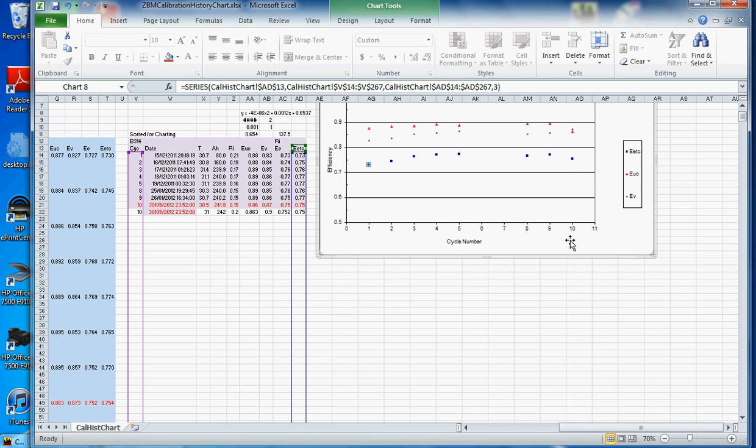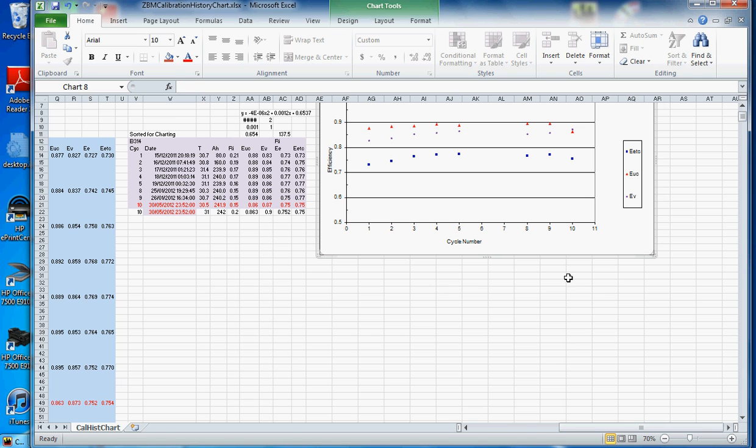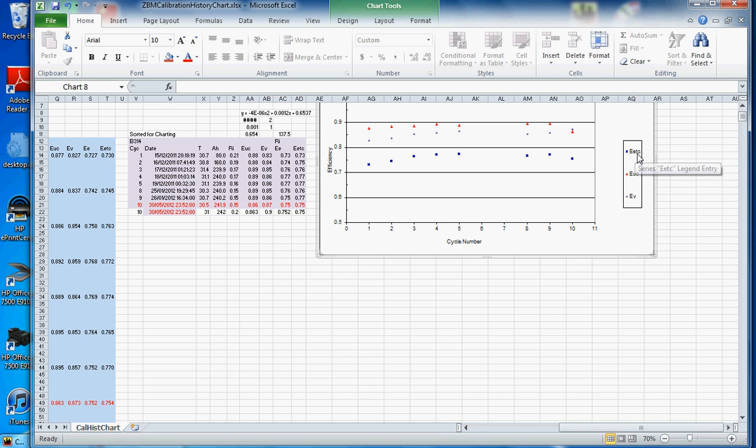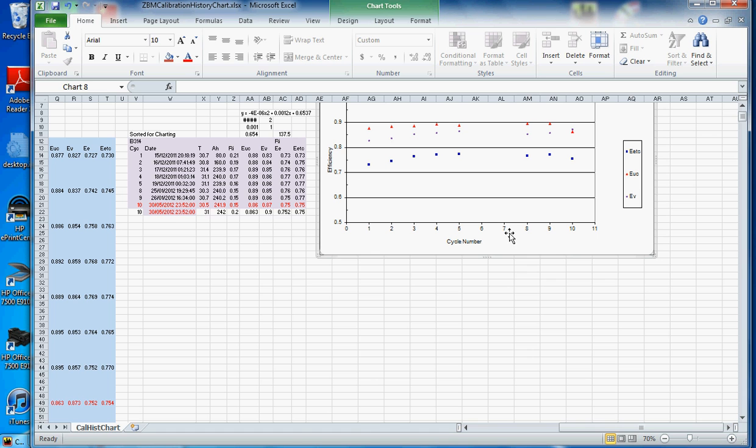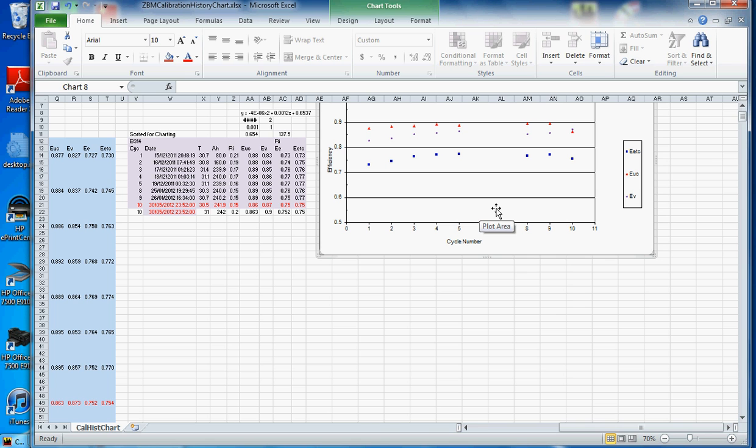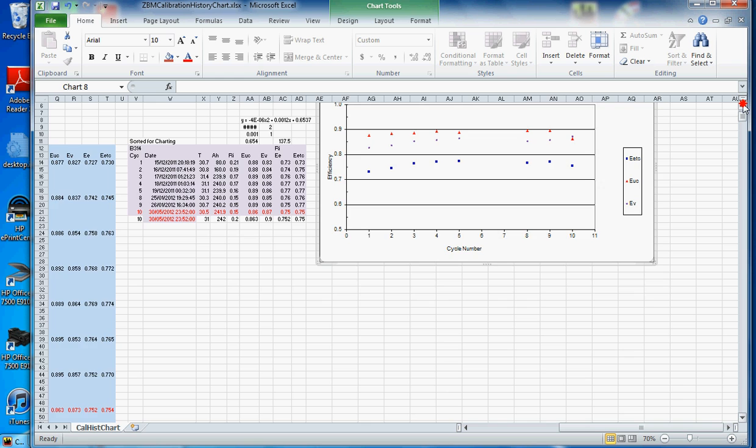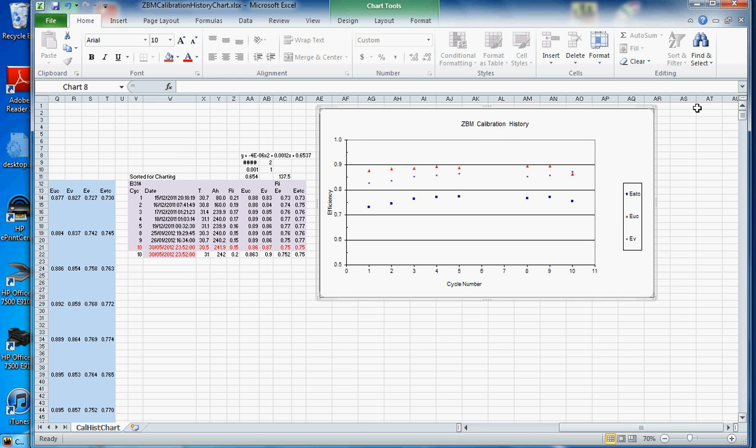And actually, I think that's the same as that line there. But the idea is that now our chart, okay, it's encompassing all of that data, is showing us here the energy efficiency temperature compensated is what that's meant to be. Over a number of cycles, we could actually chart it by date. It would be very useful to actually know what the amp hours or energy throughput was over that time. But at the very least, the energy efficiency for each calibration cycle that you perform is what we're really after in this chart, the ZBM calibration history.